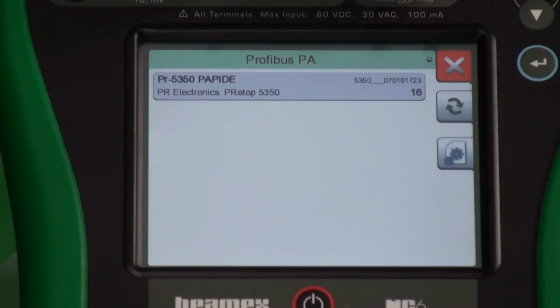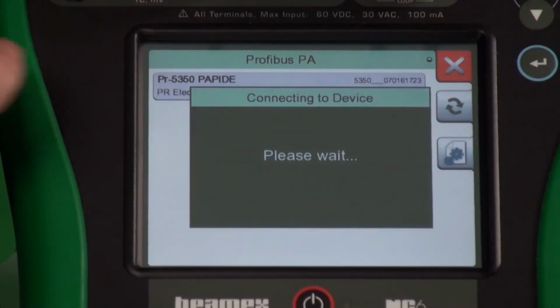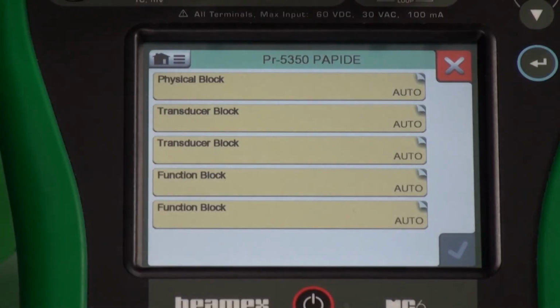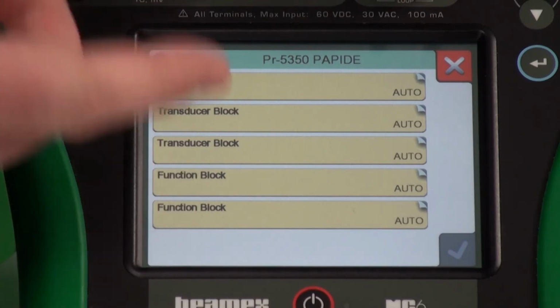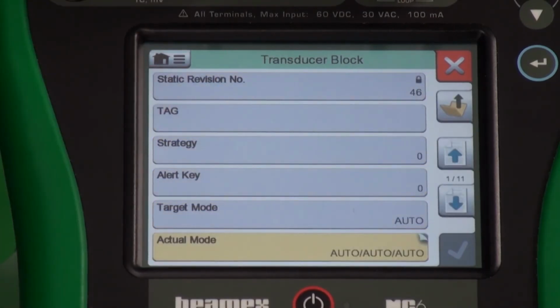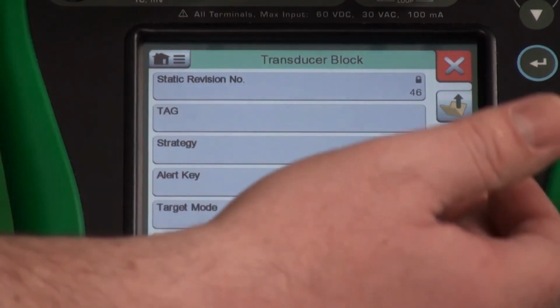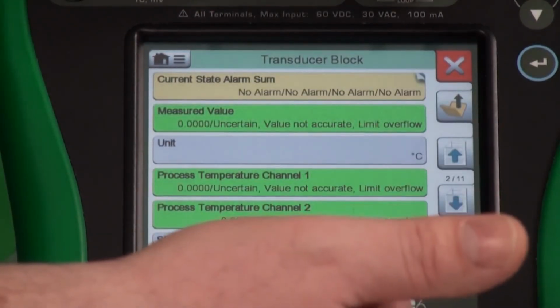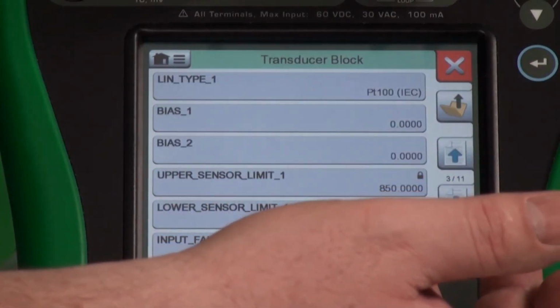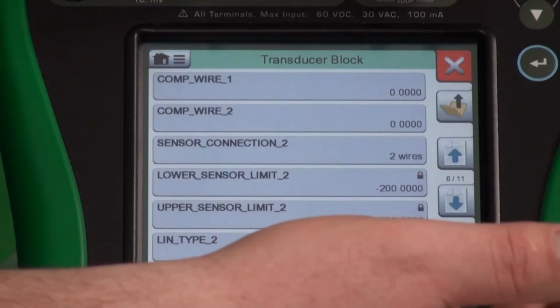We found the device. The tag name, simply select it. Now it will read in those values. All the different blocks. Let's take a look at transducer block. We have our tag. We have other information. There's 11 pages that you can go through. Remember, green is a measurable variable. Sensor limits, wire check. So you get the idea. And to go back up a level, we just hit this folder with a green arrow. That takes you up to the next level.